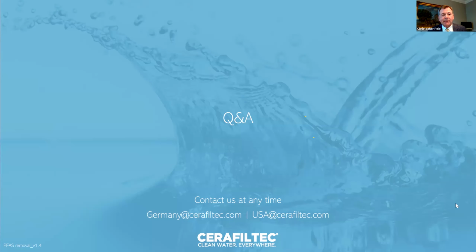It's not a permanent attachment. It's a hydraulic attachment where the powdered activated carbon is introduced violently into the influent of the dead end filtration tank, and through the ideal hydraulic design of our modules and our membranes, it's a very efficient suction, if you will, that brings the path of the water and the carbon to the surface of the membrane, where it's adhered through the transmembrane pressure, which is also what holds the carbon in place and forms that bed. So there is no chemical or physical linking other than the hydraulic forces of the water flowing through the membranes.